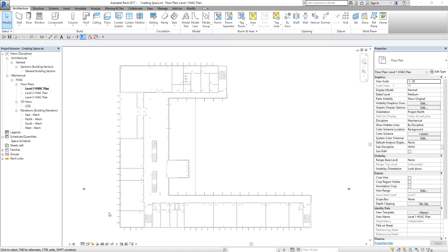We use volumes in engineering data calculations, and volumes are defined using spaces. The volume of a space defines an analytical building model which you can use for building performance analysis and heating and cooling load calculations. Spaces store values for the parameters that affect the heating and cooling load of a project. Spaces are components exclusively used in MEP disciplines to analyze volume. Spaces contain information about the location such as volumes, areas, names and numbers.